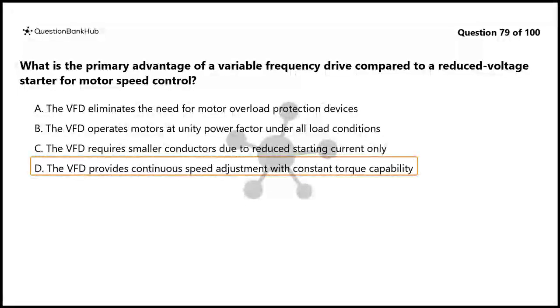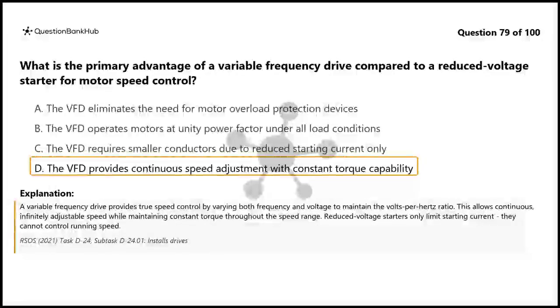The correct answer is D. The VFD provides continuous speed adjustment with constant torque capability. A variable frequency drive provides true speed control by varying both frequency and voltage to maintain the volts per hertz ratio. This allows continuous, infinitely adjustable speed while maintaining constant torque throughout the speed range. Reduced voltage starters only limit starting current, they cannot control running speed.